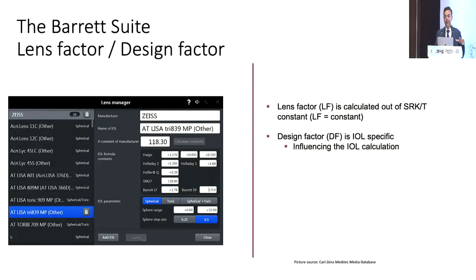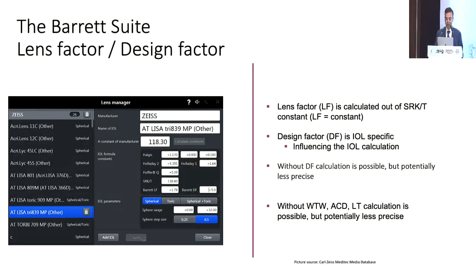Not only that we should have them, I've realized that many of our IOL companies are actually not great at entering this data into the optical biometers. I use 3 machines, the LENSTAR, the 700 and the Anterion, and I found that they have been fed with different lens factors and design factors for the same lens. So it makes the calculations totally haywire. So you have to be very careful: when you see the printout, you can check the lens factor and the design factor, and they should be identical on all machines for the same lens type. Otherwise it will go totally wrong, and your measurements will not be precise.